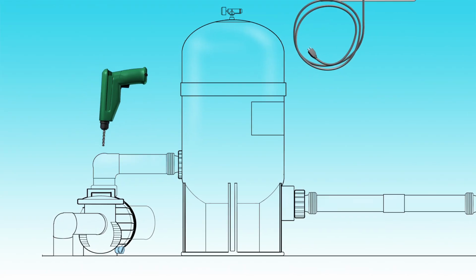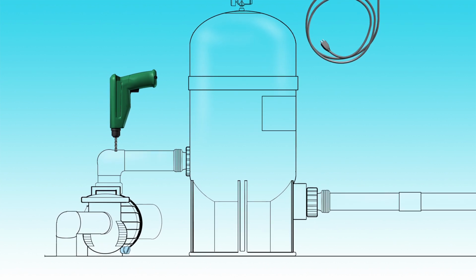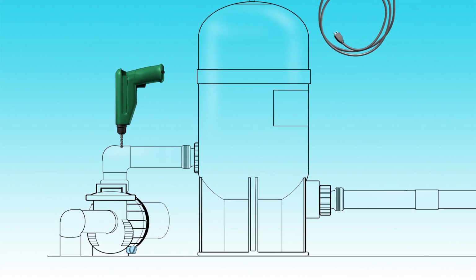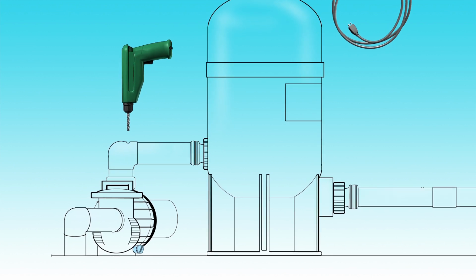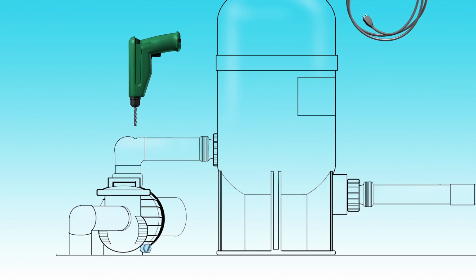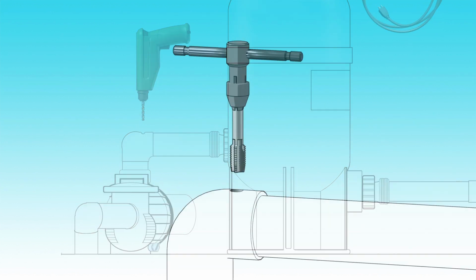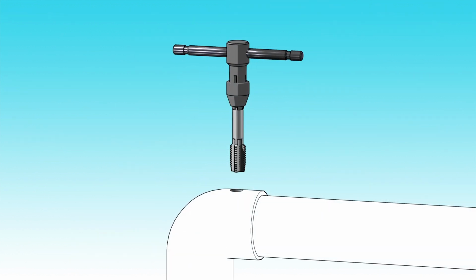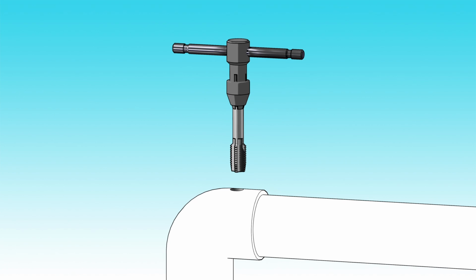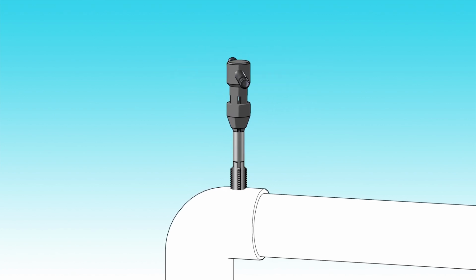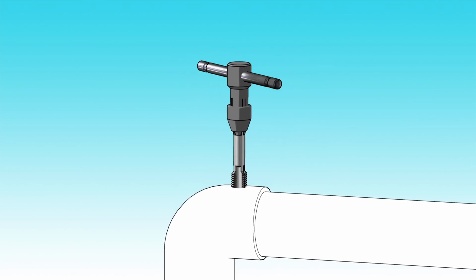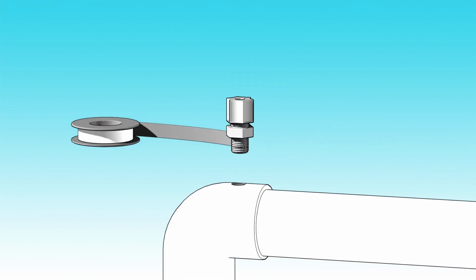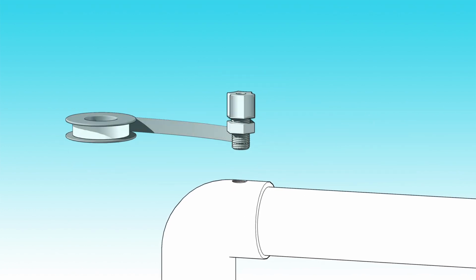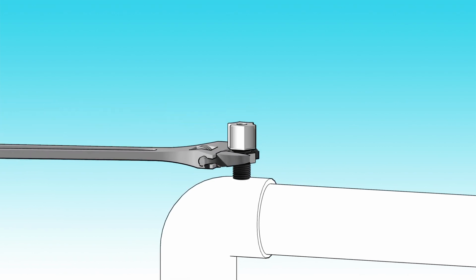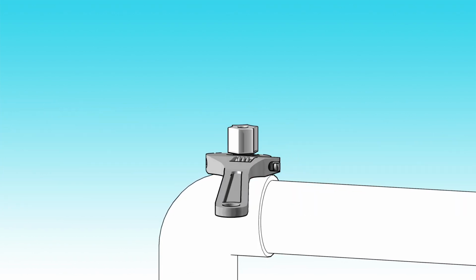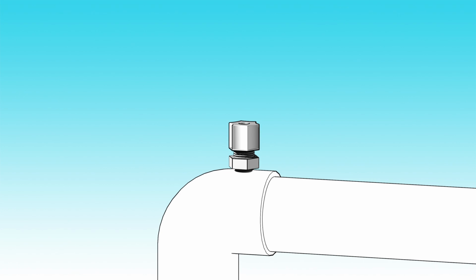Drill a 7/16-inch hole in the pump elbow, upstream from the filter. This will bring fresh water into the flow cell. Drilling into a fitting on the pipe provides a more substantial area for the threads. Tap a 1/4-inch NPT port. Wrap the threaded end of the compression fitting with Teflon tape. Insert the fitting into the tapped hole and tighten. Be careful not to over-tighten the fitting.